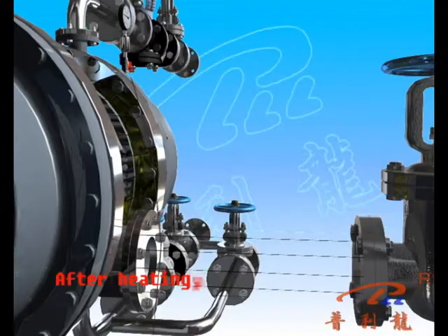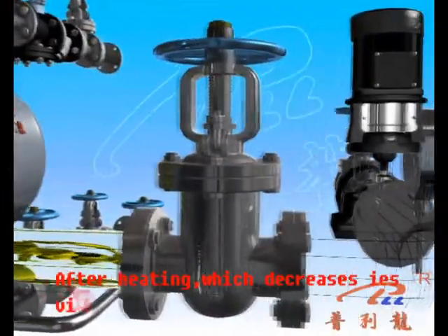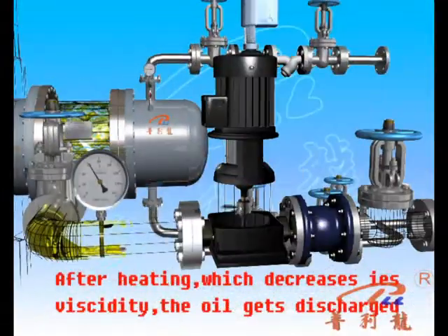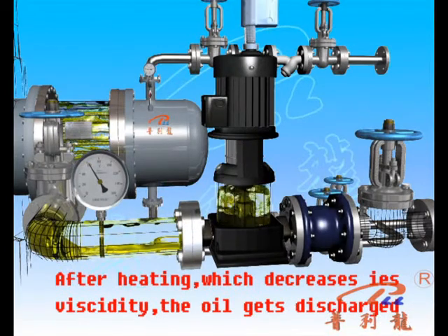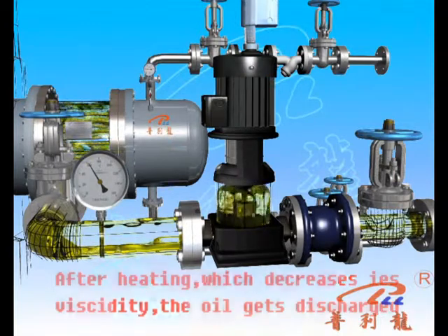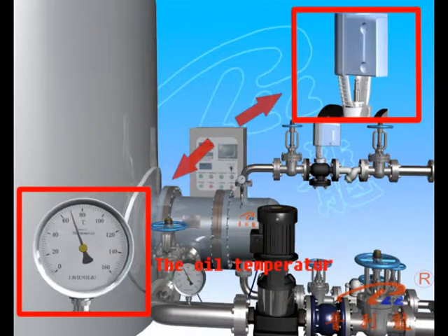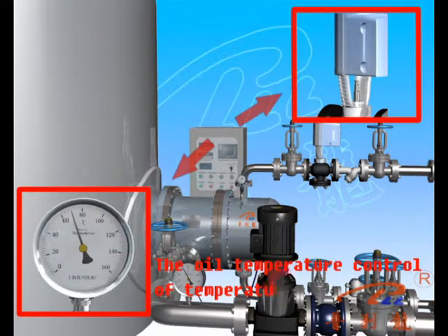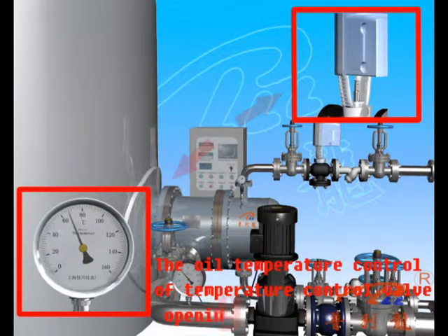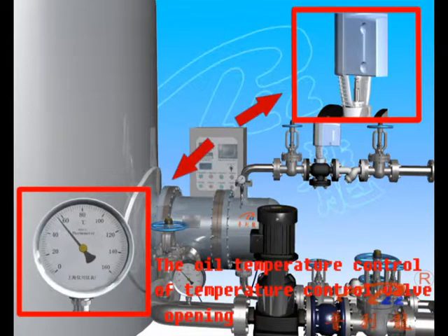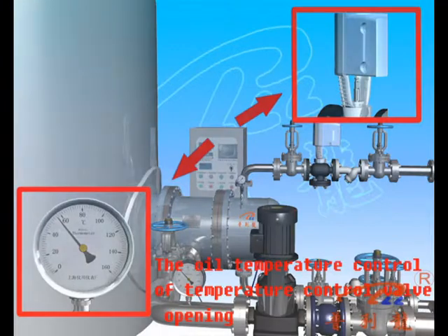The temperature of the oil increases through heating, which decreases its viscosity. The oil transfer pump discharges the oil from the oil tank. A temperature control valve is fixed at the steam outlet of the heat exchanger to control the steam outlet volume by using the oil outlet temperature measured by the heat detector at the oil outlet. In this way, the temperature control valve can ensure a constant oil temperature.